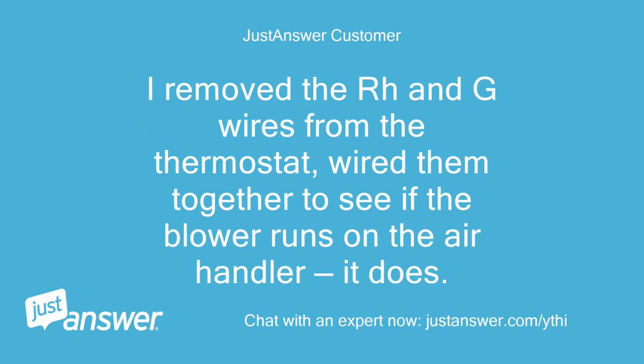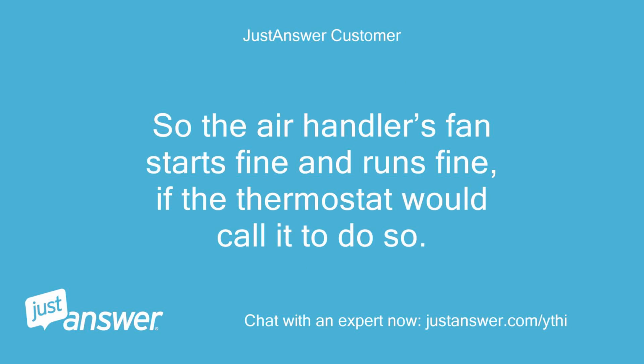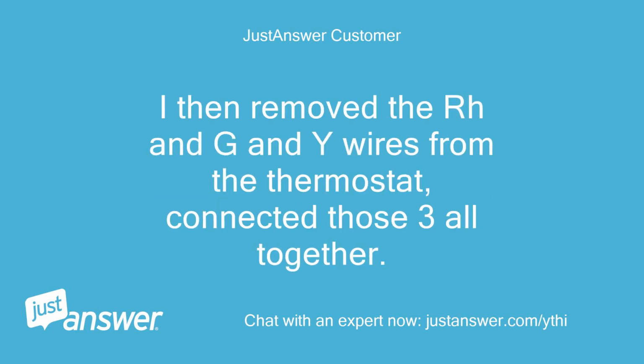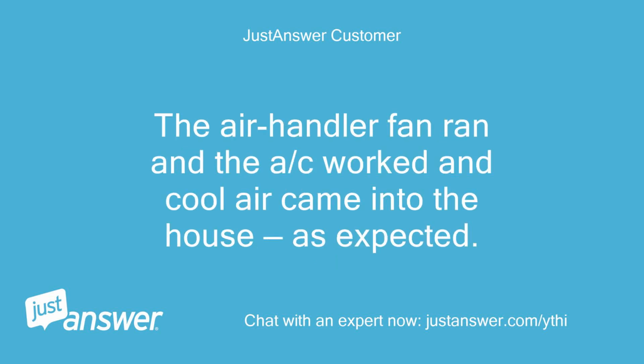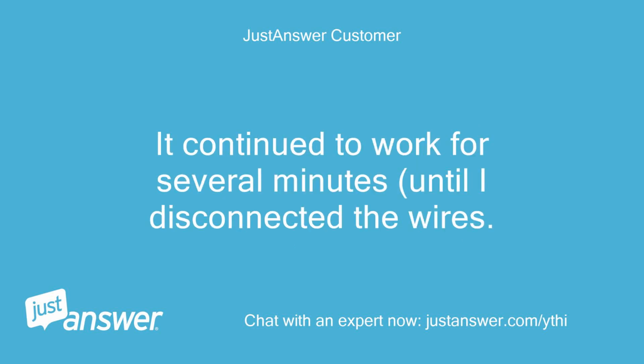I removed the RH and G wires from the thermostat, wired them together to see if the blower runs on the air handler. It does. So the air handler's fan starts fine and runs fine, if the thermostat would call it to do so. I then removed the RH and G and Y wires from the thermostat, connected those three all together. The air handler fan ran and the AC worked and cool air came into the house, as expected. It continued to work for several minutes, until I disconnected the wires.